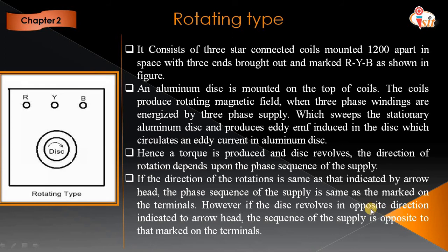If the disc revolves in the opposite direction to the arrowhead, then this phase sequence is incorrect.